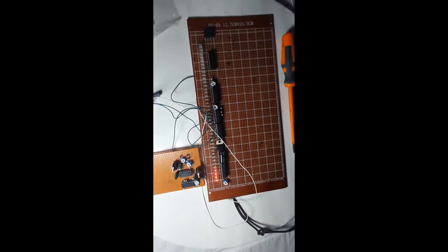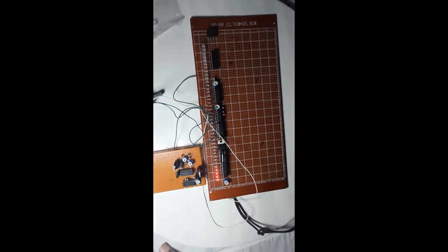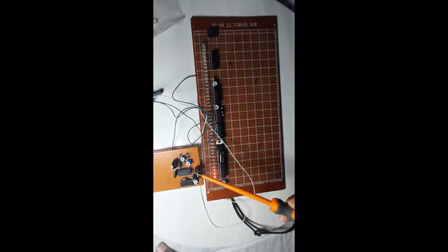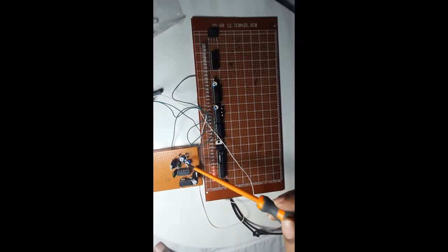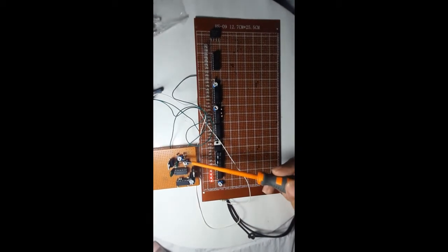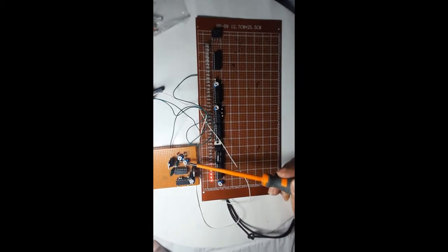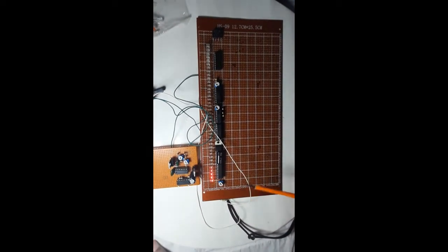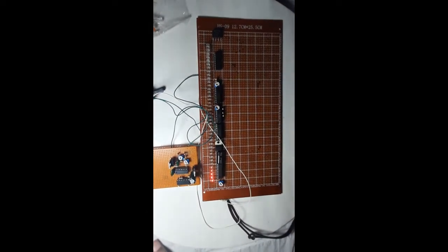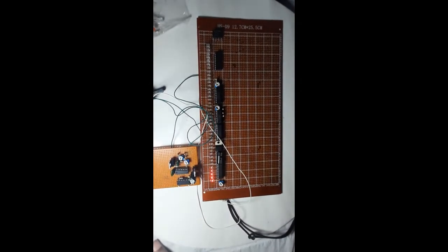But I will correct the zero error first. To correct the zero errors, there are a couple of ways. This is the 4-20 signal generator, and here you can see the variable resistors, small potentiometers. We call those presets. By turning these two, we can do that. One is to correct the zero error, the other one is to correct the span error. And here also you get two pots. This pot is to correct the span error, and this is to correct the zero error.